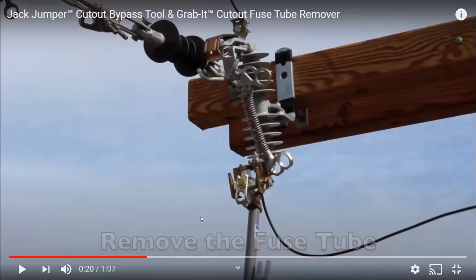Okay, so in these cases right here, you've got to watch some safety things going on. This is the jack jumper right here, and we use them a lot on our system. Your electrical flow now is from the high side riser through the switch, through the jack jumper, and this is not a bolted connection, it's just a spring-loaded connection through the low side riser to wherever it's going. So power current flow has not been interrupted. The thing you've got to look out for here, and I've seen employees do it, is they'll open the fuse up and then go up there with their rubber gloves, and they'll do what?